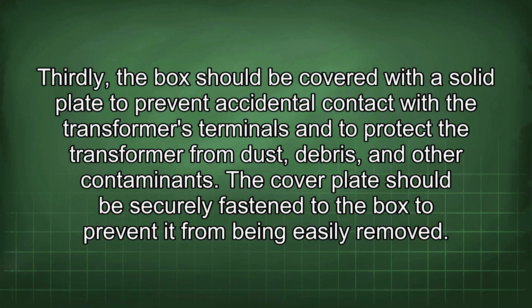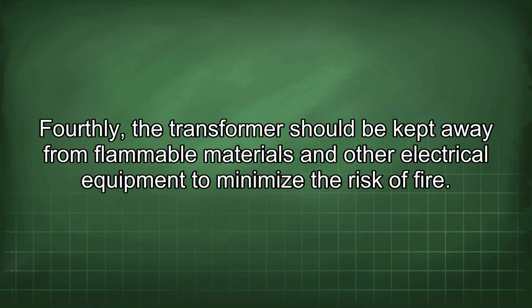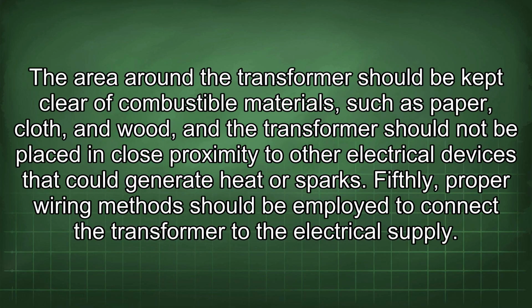The cover plate should be securely fastened to the box to prevent it from being easily removed. Fourthly, the transformer should be kept away from flammable materials and other electrical equipment to minimize the risk of fire. The area around the transformer should be kept clear of combustible materials such as paper, cloth, and wood, and the transformer should not be placed in close proximity to other electrical devices that could generate heat or sparks.